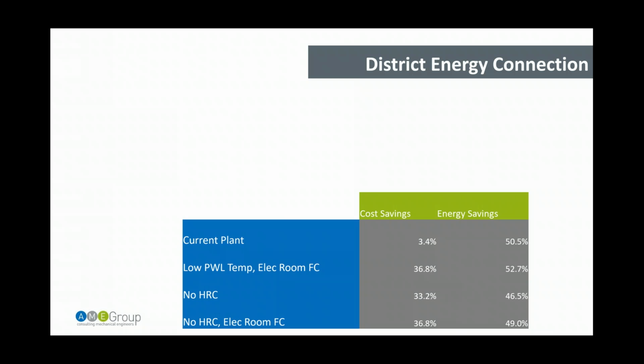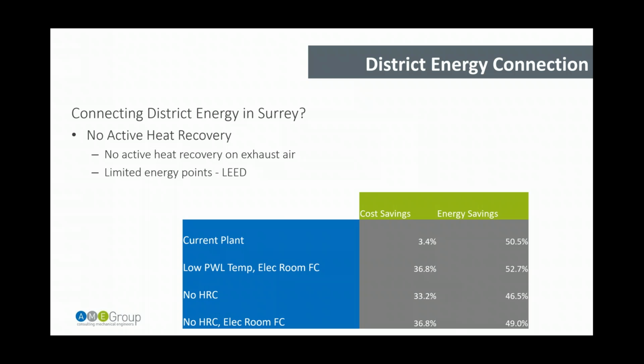The next challenge that we had was district energy. In the Lower Mainland, district energy is a pretty big thing that started about 15 years ago, and the city of Surrey has a district energy connection requirement in the area that we're at. Unfortunately, they mandate requirements around heat recovery, and they mandated that we couldn't have active heat recovery in our exhaust air stream. It also limited how many LEED energy points we could get, at 10, because the district system was pretty new, and they didn't have any metrics on how efficient their system was. So that limited what we might look at in terms of using an active chilled coil on the exhaust air stream.